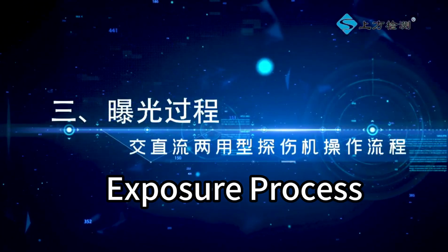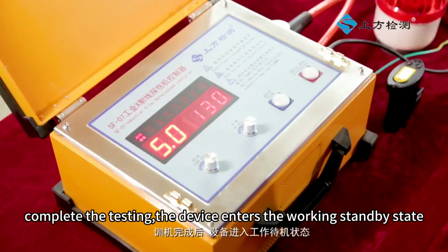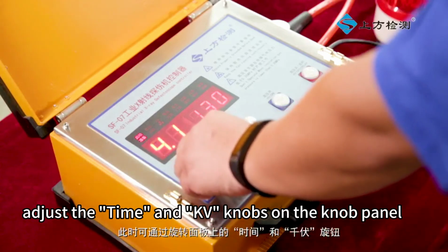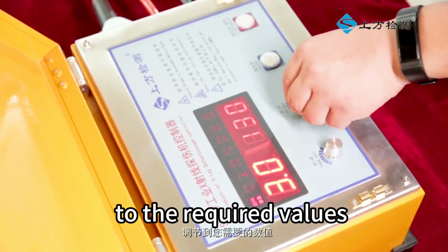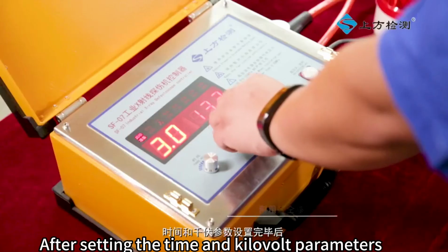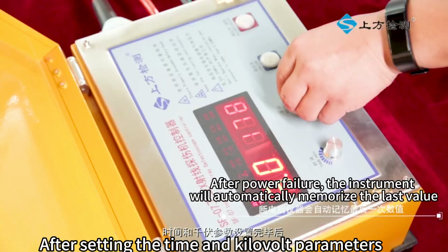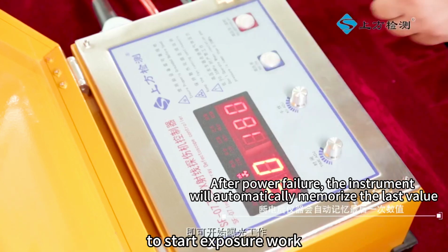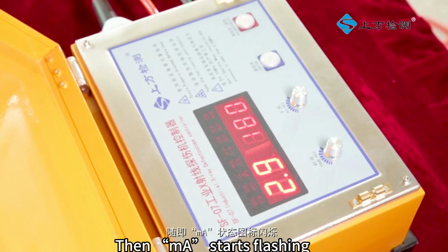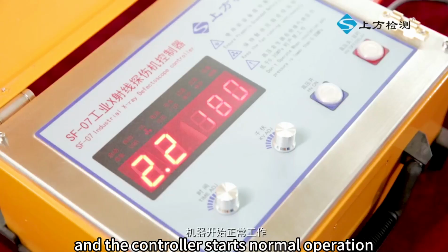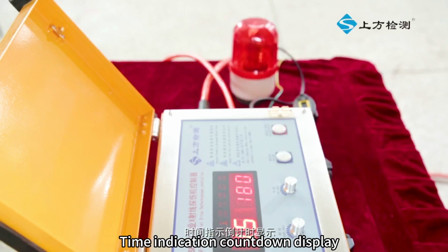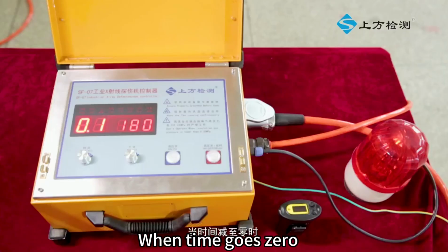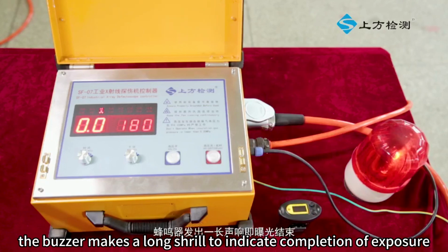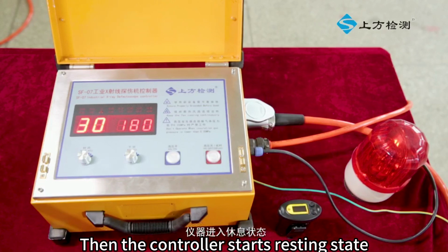3. Exposure process. After completing the testing, the device enters the working standby state. Adjust the time and kV knobs on the knob panel to the required values. After setting the time and kilovolt parameters, press the HV on button to start exposure work, then the mA status icon indicator flashes and the controller starts normal operation. The time indication counts down. When the time reaches 0, the buzzer makes a long shrill to indicate completion of exposure. Then the controller starts the resting state.